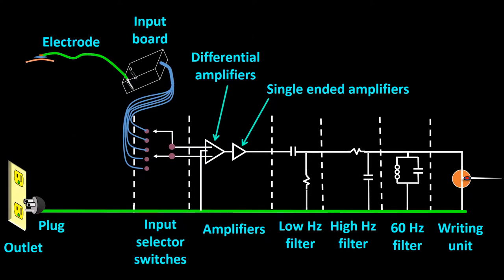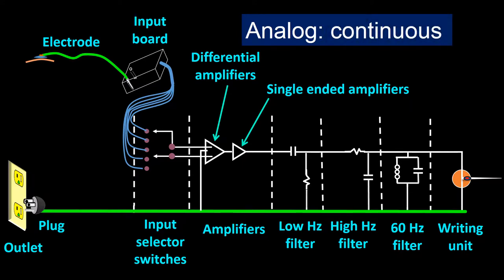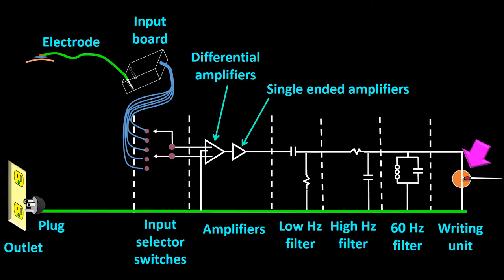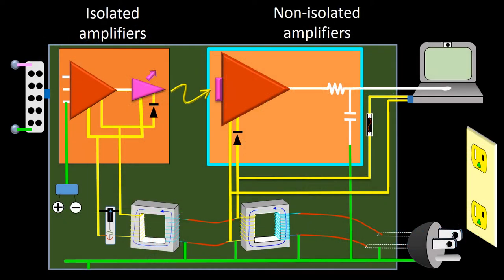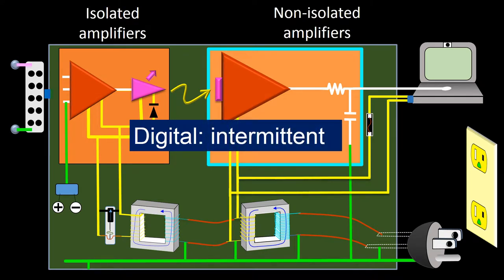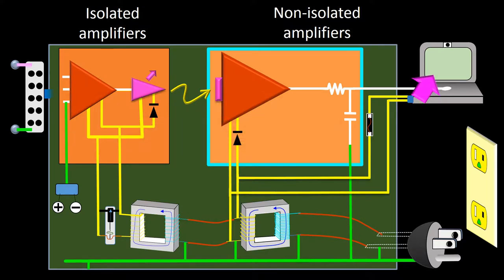This is the model of an old EEG machine. They were analog machines with continuous data recording translated to paper by an oscillographic pen writer device. This is the model of a new EEG machine. The new EEG machines are digital. They collect data points intermittently from the analog signal generated by the brain electrical activity and reproduce it by reconstructing the activity in the form of a continuous wave on the computer screen.